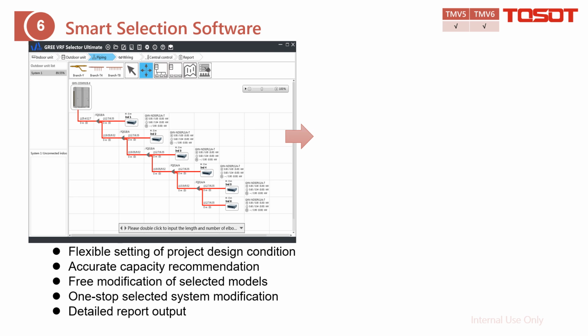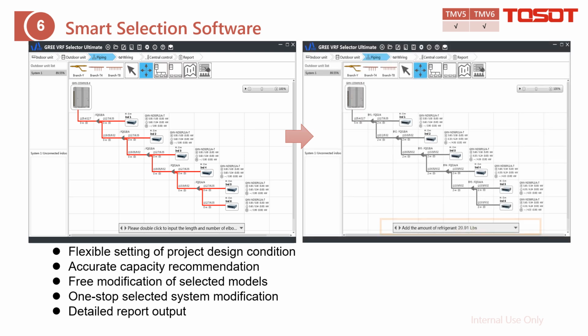Selection software, also called the VRF selector. From here, we allow you to select the indoor unit and then select the outdoor unit. Then after you input the pipeline information, the system can automatically calculate the additional refrigerant for the system. And also for this example, when you select the indoor unit and the outdoor unit and combine them together, and after you input the information of the pipeline, you can find it can automatically show you the additional refrigerant amount. Also, it can give you a detailed report for your projects.